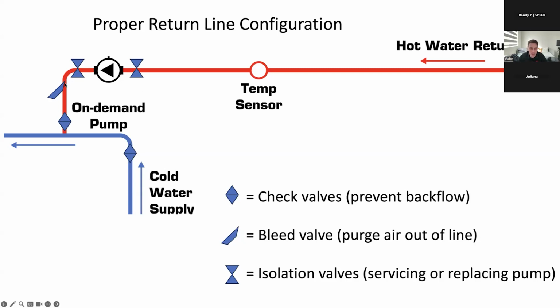And a bleeder valve is just like a hose bib that you put downstream of the pump. And if you ever run into a situation where the pump is running, but the return line is not getting hot, and the pump itself is burning hot to the touch, that's the surest sign that you have airlock. All you have to do is open up that hose bib, that bleeder valve, attach a hose to it and run the hose outside into the front yard or whatever, and you'll see that air getting purged out of your return line.